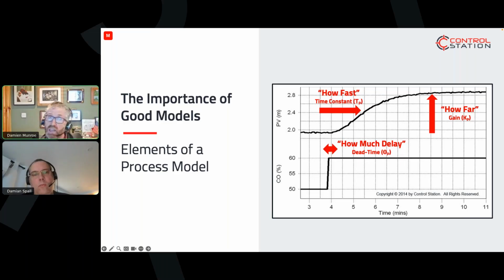That lag, that delay, we have to wait for it - the control system has to wait for that. So really that dead time is key to getting good control: the longer that is, the softer your control has to be. The time constant is how quickly - if the process takes 15 minutes to change, you're not going to be able to change that time into 5 minutes. It's something that's locked into the process.